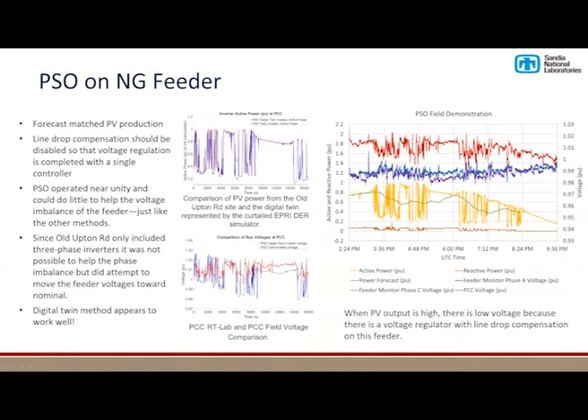The first thing is, in the image in the upper left, you can see active power for the digital twin and the field inverter, and they match quite well. We're monitoring the inverter in the field and then setting a curtailment level in the simulated device to match that. For the comparison of bus voltages at the point of common coupling, it's a little bit off. This could be partly due to the other voltage regulation equipment that we're not accounting for and don't have visibility into. But overall, the trends match reasonably well, I would argue pretty well.